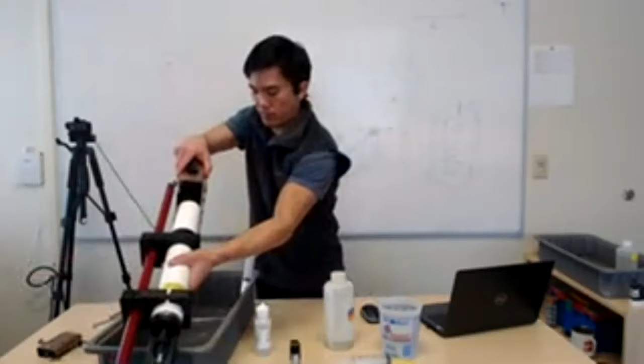We're going to move it back and forth, and you'll see the bubbles forming. Just do this for about 30 to 60 seconds or so, agitating anything in there. This is going to remove any oil, any biofouling that may have found its way inside of your flow path. And then remove it, dump it out. And then repeat this process with clean deionized water to get rid of all the soap. Once you don't see any bubbles coming out of the other tube, you know that you've removed most, if not all, of the cleaning solution, and your instrument is ready to deploy.